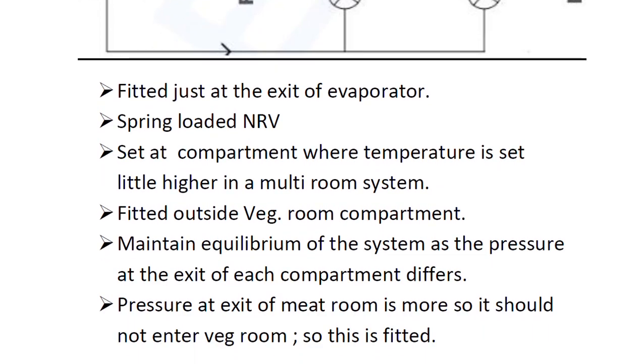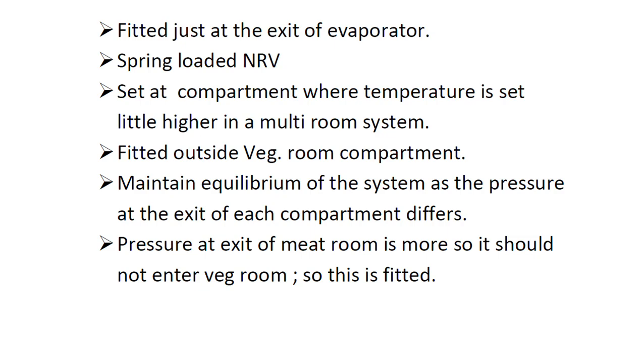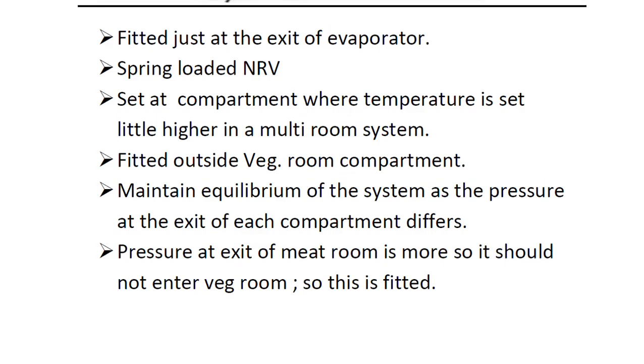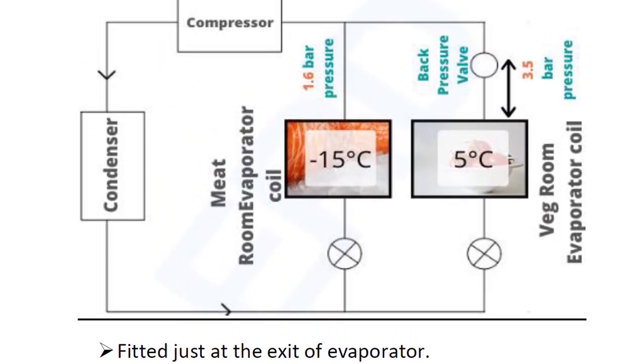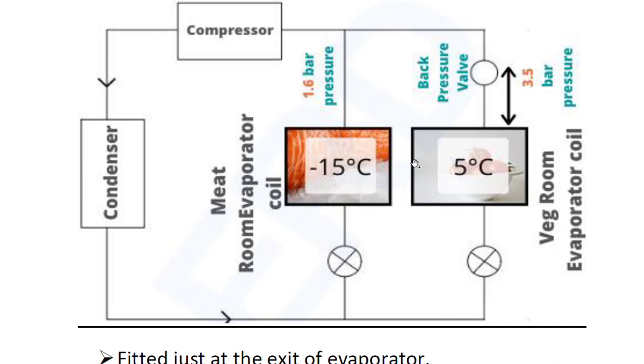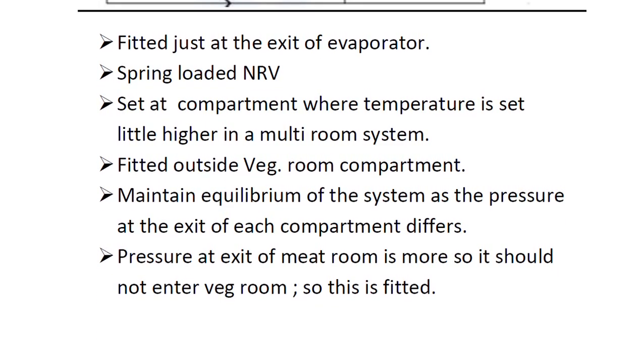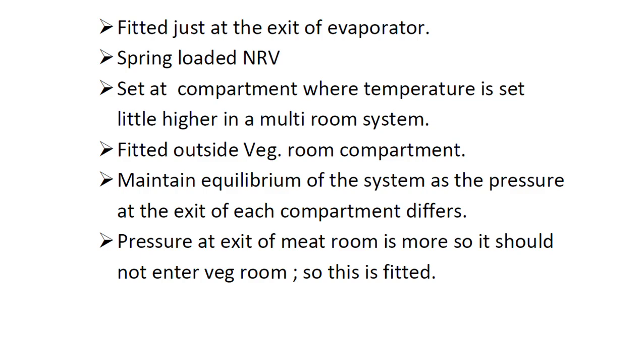Now let's look at the function. The back pressure valve is fitted just at the exit of the evaporator. It is a spring-loaded NRV — non-return valve — set at the compartment where the temperature is set a little higher in the multi-room system. Since the temperature in the veg room is set higher compared to the meat room, it is fitted outside the veg room compartment to maintain equilibrium of the system, as the pressure at the exit of each compartment differs.